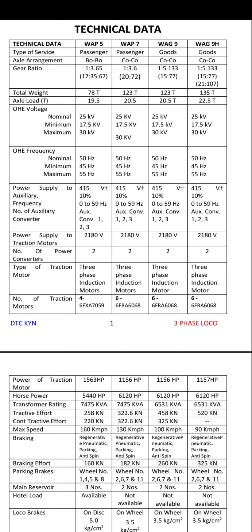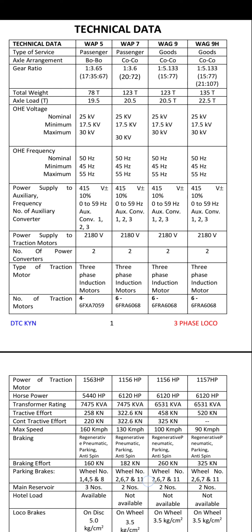OHE voltage is 25 kV in each case. For minimum voltage, it can run for some time at 17.5 kV, and if the OHE voltage rises, it can still run for some time up to a maximum of 30 kV. OHE frequency is 50 Hz plus or minus 5 Hz.